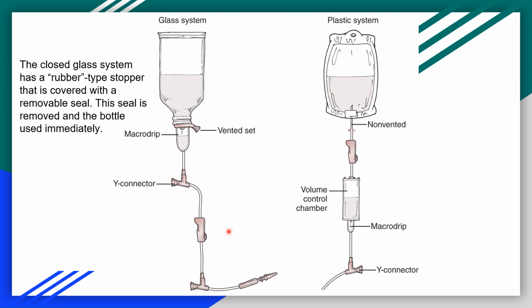Now, what I want to point out is this tubing has a flow regulator, a roller clamp that regulates the flow if this is open to gravity. If this is hooked to a pump, it would be opened all the way, so then the pump regulates the flow. However, if you're doing this in a home environment, or in some clinics, and you don't have a pump, you're setting the drip rate based on a calculation, and you regulate it with this.